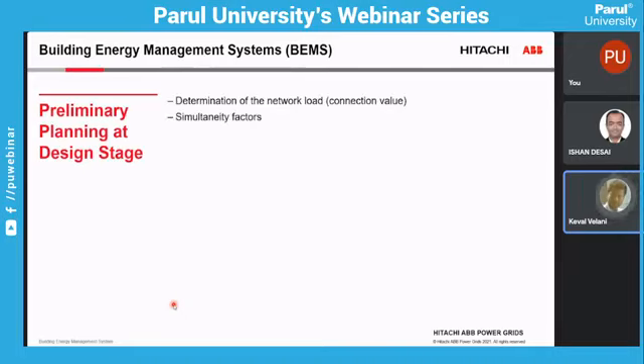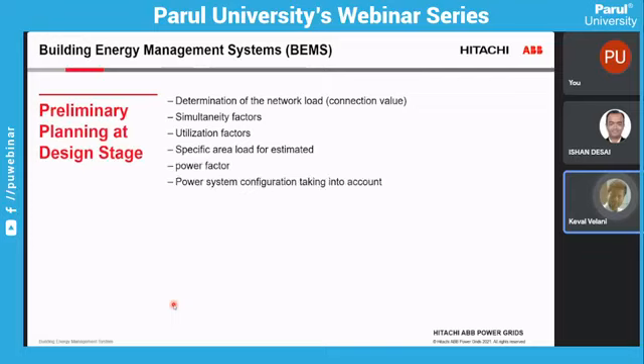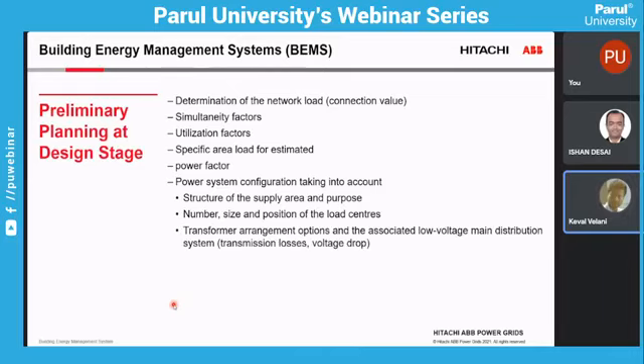Determination of the network load simultaneity factor, then utilization factor, specific area load for estimation, then what is your power factor, then the power system configuration, structure of the power system configuration, taking into account the structure of the supply area and purpose, number of load centers, size of the load center, and position of the load centers. Transformer arrangements: how distribution transformers are arranged, or how you manage power demand within the distribution transformer.